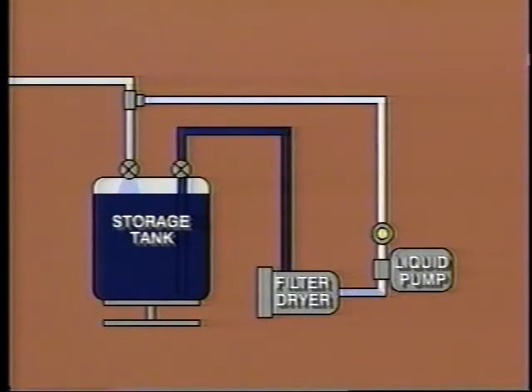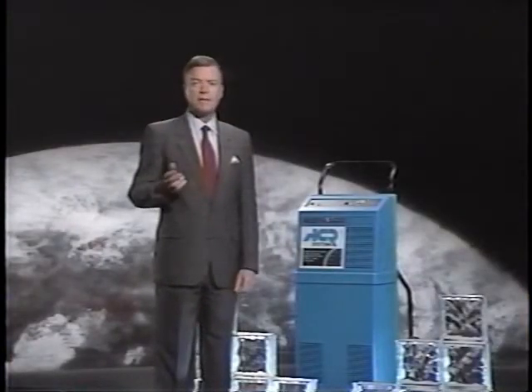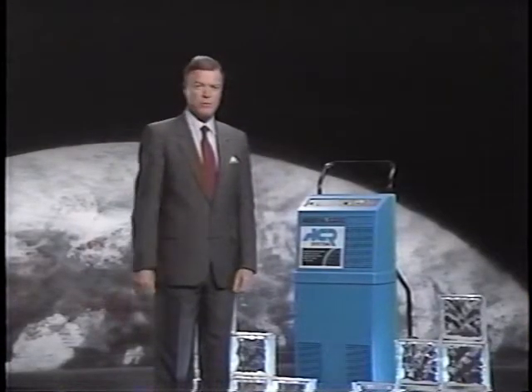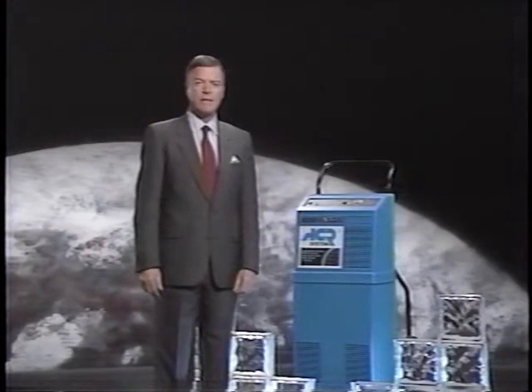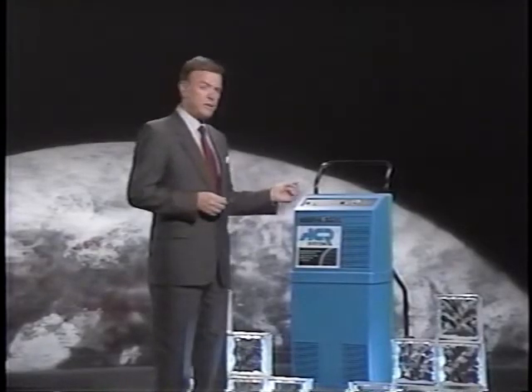The pump recirculates refrigerant through the system. When the moisture indicator is green, the R12 is clean. Shut off the system. Recycling time is 30 minutes to 2 hours, depending on refrigerant quantity, moisture content, and condition of the filter dryer core. Now, let's look at usage.